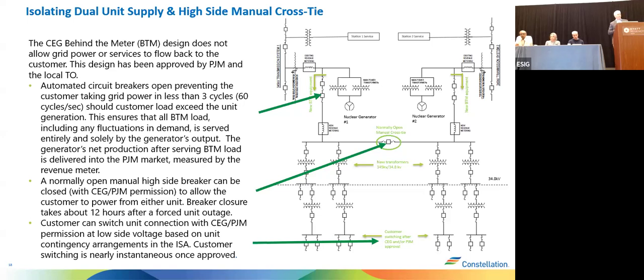We've set up a set of circuit breakers that will open if, for instance, the reactor goes out of service, so the customer loses power on a single feed - ensuring we're not bringing power back in from the grid to the customer. We also have a cross-connect in the drawing, allowing power to be closed if one reactor is out of service, so the customer's load can always be served by the in-service reactor.